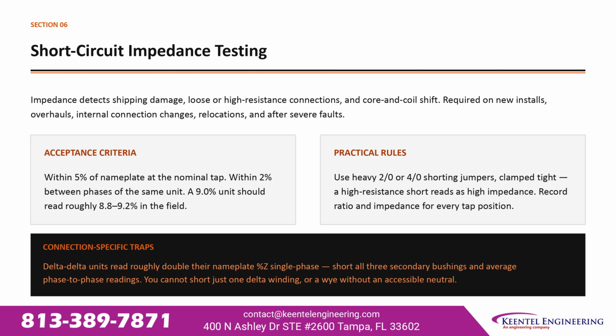Impedance testing detects shipping damage, loose or high resistance connections, and core and coil shift. It's required on new installs, overhauls, internal connection changes, relocations, and after severe faults. The acceptance criteria: within 5% of nameplate at the nominal tap and within 2% between phases of the same unit. A 9.0% unit should read roughly 8.8 to 9.2% in the field. Practically, use heavy 2-0 or 4-0 shorting jumpers, clamped tight. A high-resistance short reads as high impedance.